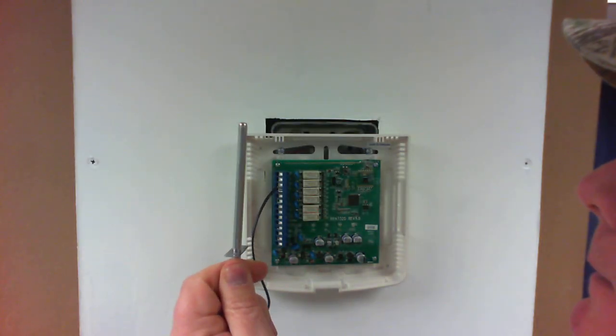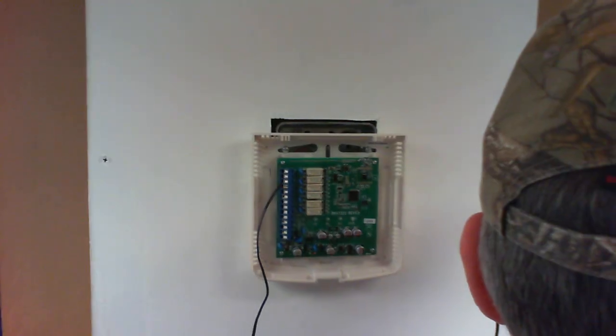What is it, you ask? Why do I need it? Where do I put it? So let me back this up just a little bit. The plenum sensor is meant to be installed in the return air plenum on a forced air system. What this does is it serves as a backup or a fail-safe in the event that the wireless thermostat loses communication with the control module. As long as the wireless thermostat is communicating to the control module, then this plenum sensor does nothing. It just sits there. Doesn't do anything at all.